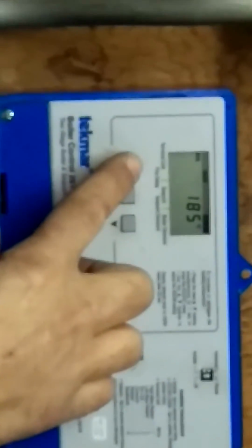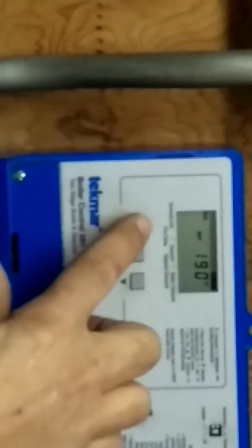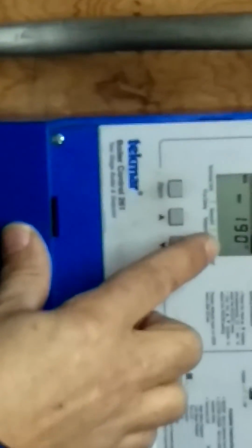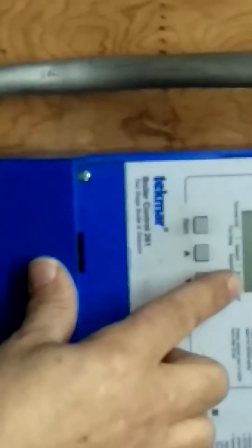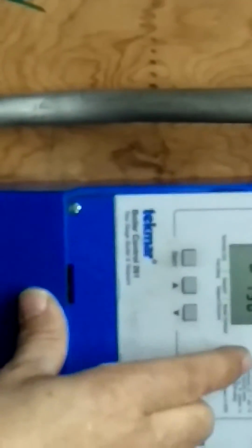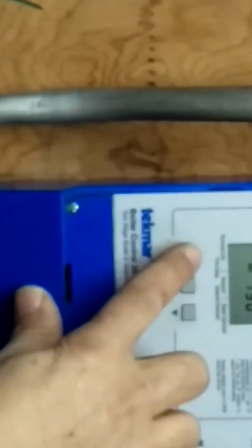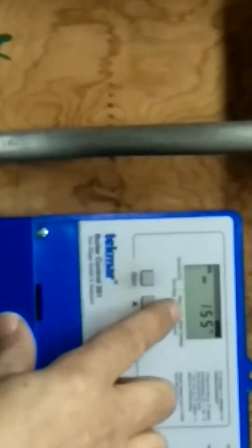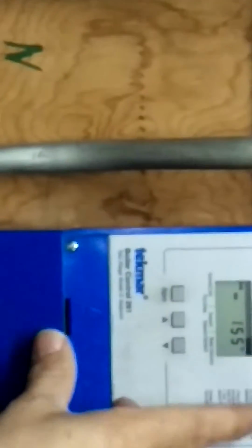Actually, we can go up to 190 if we wanted to, but that's okay, because the boiler's keeping up with the building heat. Next one is max. We usually go 5 degrees higher, so that as it gets colder, it can go up a little higher yet. So max boiler is at 190. Minimum, I'm going to bring down to 155 just for now, because it's cold enough that it's going to stay up. So minimum normally would be at 140. 145 is a good number though, or even up to 155.